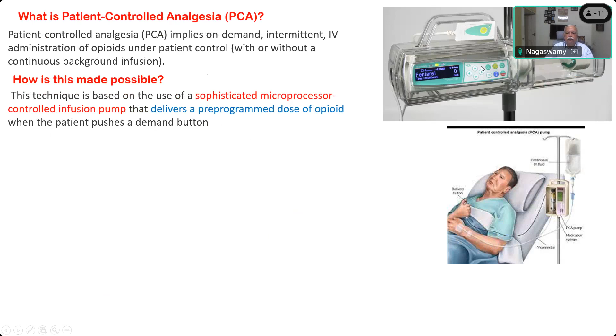So how could this patient-controlled analgesia be brought into clinical practice? How this was made possible is, the technique is based on use of a sophisticated microprocessor controlled infusion pump that delivers a pre-programmed dose of opioid when the patient pushes a demand button. So this is how the mechanism works. You can see this is the pump, and this is the control button in a different form. The yellow button in the center is what the patient presses, and it will deliver.